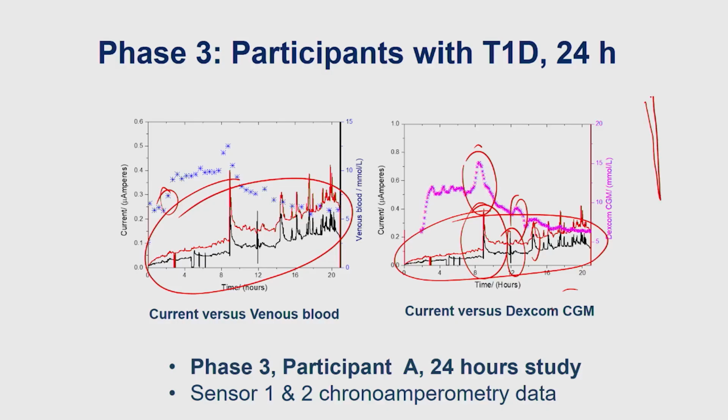The reason I have understood that is when a sensor goes into the skin, the interstitial fluid is not like a continuous flow. It's in the form of droplets. I think all these droplets go together around the sensor surface, and then they coalesce. They aggregate and form a continuous layer, and then it starts. So that's what we call a sensor warm-up time.